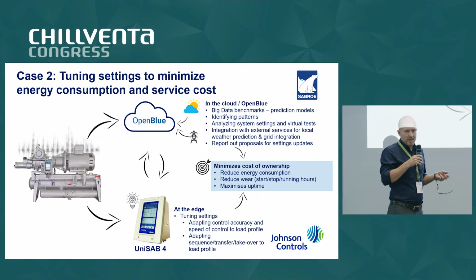When a new plant is commissioned, the commissioning technicians configure the settings in the local controllers to fit the load profile of the actual plant. But nothing is static in this life, nor is the use of the plant. Wear of the machines kicks in right from the beginning, along with changes to operating conditions on the cold and hot side of the equipment. Load profiles change, customers sometimes change the use of the plant, meaning that the settings configured at commissioning no longer fit.